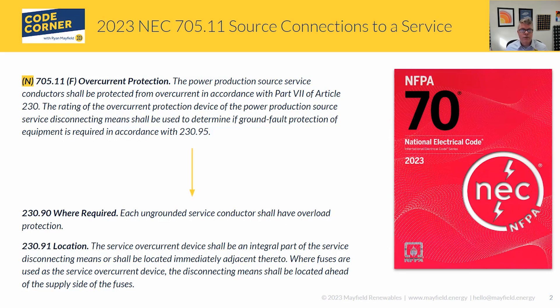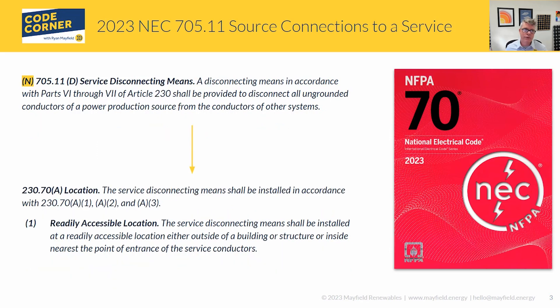Reading through Part 7, it talks about the requirement for overload protection and the location of overcurrent devices, but it doesn't tell us how far away they can be — unlike the 2020 code. So you're left looking for a bit more. One place to look is 705.11D, which is system service disconnecting means. Again, it points us back to Article 230 — Part 6 and Part 7 — for these disconnecting means.